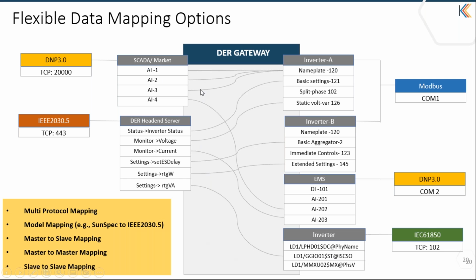So the mapping framework of the gateway is flexible, so that you can ensure there's a multi-protocol mapping. You can map the same data to different systems using a master to slave mapping. So this is the master interface, which is responsible for collecting data from the field devices. And this is the slave or server interface, which is responsible for giving out data to external systems. So the default is often master to slave mapping. You can map the master to a slave, so that data from the field devices can go directly to the SCADA systems or ADMS systems.